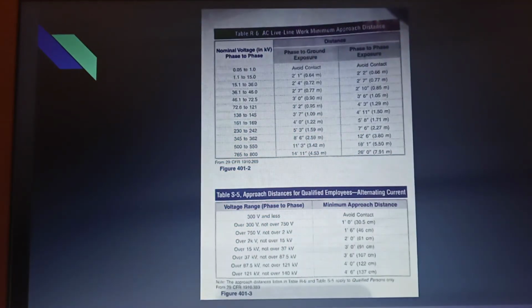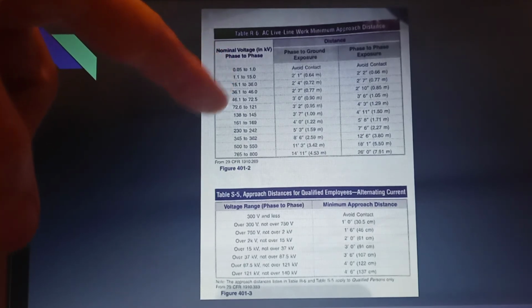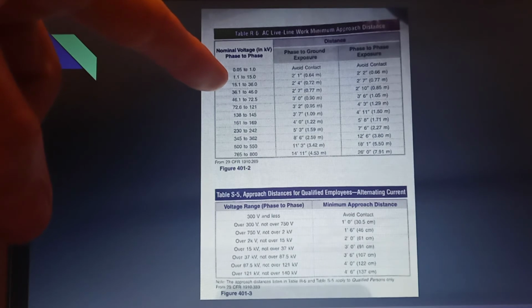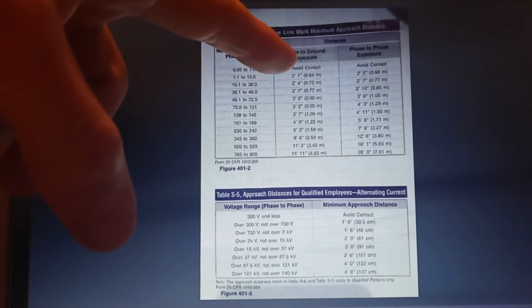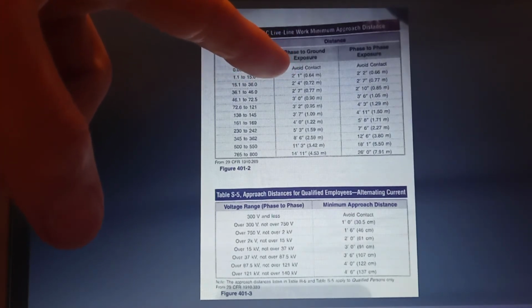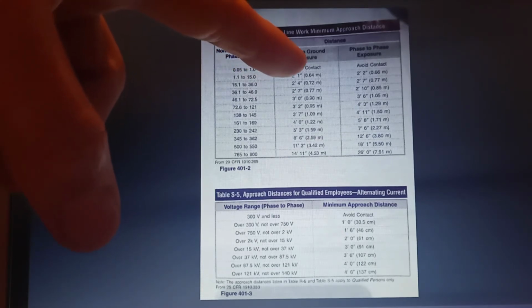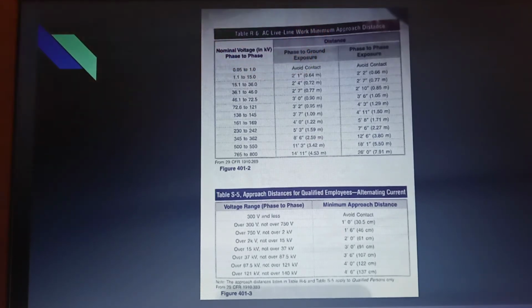And then here's another table that shows you line work, for AC live line work, and it's your approach distances. I'm not going to do them all, but we will do this. The nominal voltage over here to the left is in kilovolts, phase to phase. So we'll do the 1.1 to 15 kilovolts, and it says for the phase to ground exposure, you should be 2 foot 1 inch away, and for the phase to phase exposure, you should be 2 foot 2 inches away.